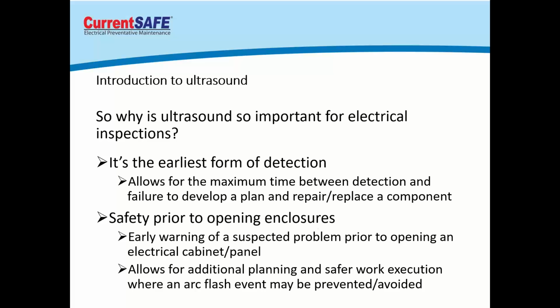It's also used as a safety tool for our technicians before they open any electrical panels, cabinets, or enclosures, because we can hear around all the little gaps and cracks manufacturers build in for ventilation and listen for any arcing, tracking, or corona going on in the cabinet. That early detection may be a warning sign that we don't want to open that gear if there's already a problem behind there.